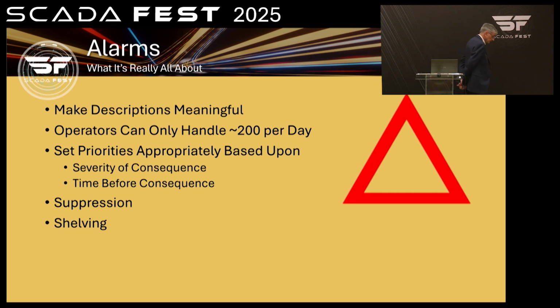Shelving is a really powerful tool in VT SCADA. You can go to the alarm page, pick an alarm or an area, and shelve the alarm. Shelving means that you take it out of service, but only for a limited period of time. The kind of thing you do is, someone's doing maintenance on a piece of equipment. Again, they're testing meters and timing them from low range to high range to see if they're all calibrated right. You don't want those things to generate alarms, so you can shelve those alarms while someone's working on it.